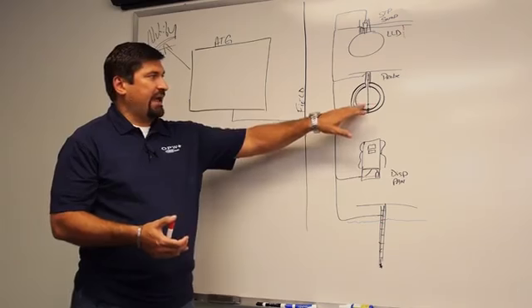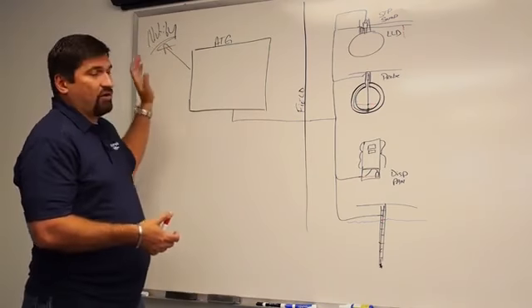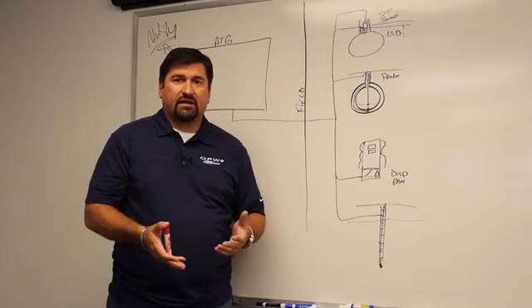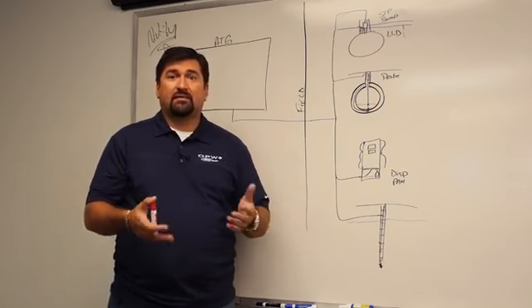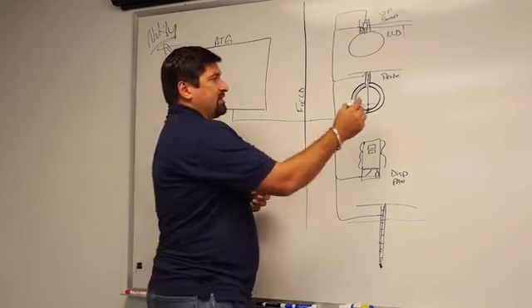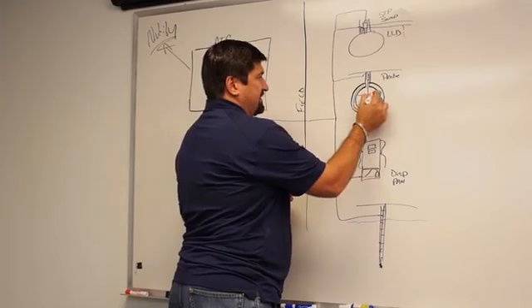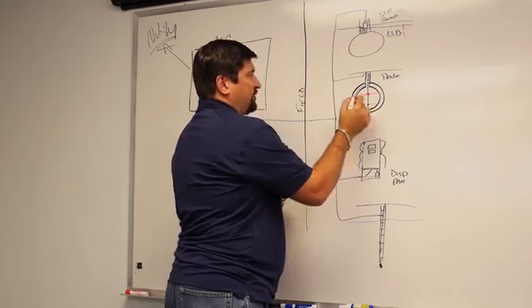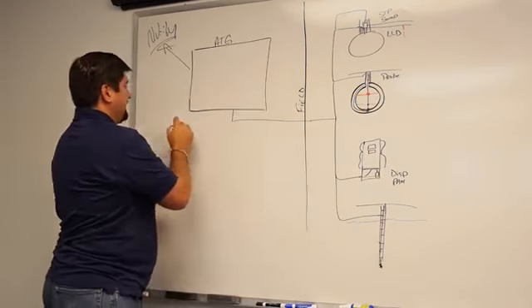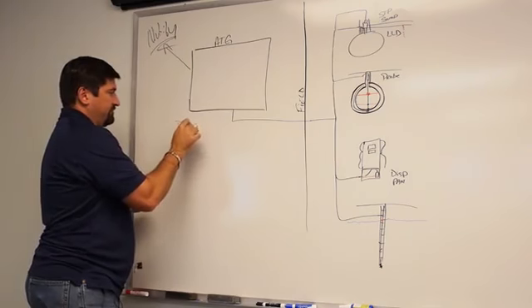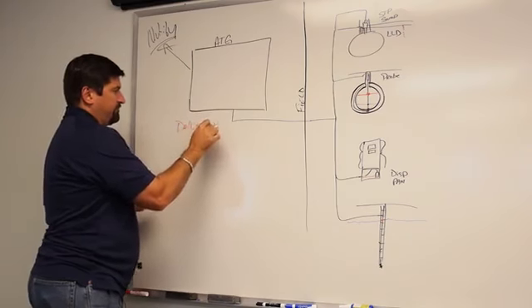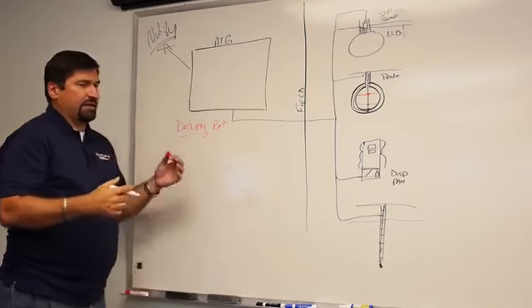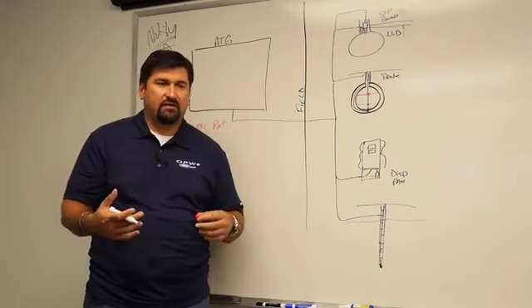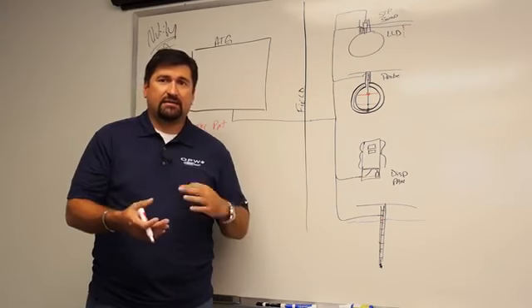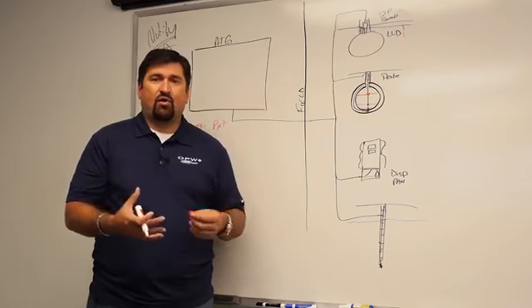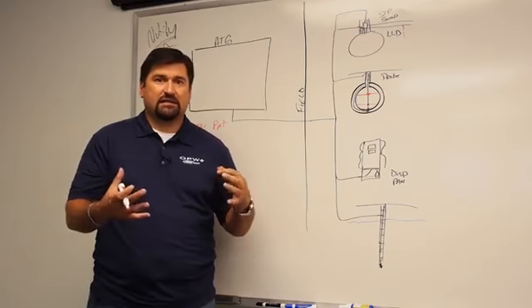I can have it automatically send out a notification to a delivery company that, hey, I need product and I'm getting ready to run low. And then it comes back as soon as your delivery is in the tank. It tells you how much product was delivered and gives you a delivery report. This delivery report gives you your beginning volume, your ending volume, your starting height, your ending height, and the temperature of the product. It gives you the whole aspect of what was physically delivered.